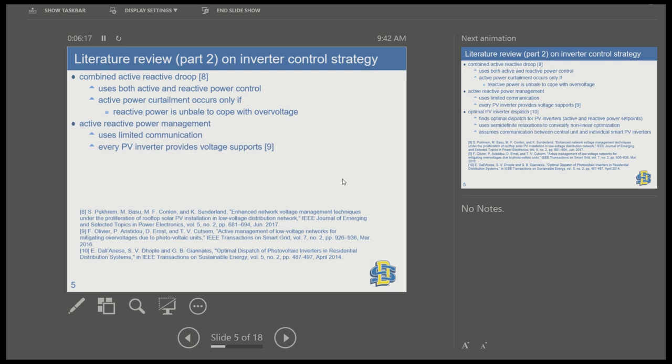All of these are still local controls — they use only local information, such as the voltage at the point of connection and current. Another approach is active reactive power management, which uses limited communication to issue a signal to all PV inverters that an overvoltage has occurred. They will then coordinately absorb reactive power and curtail active power, which has the benefit of minimizing total energy curtailment.